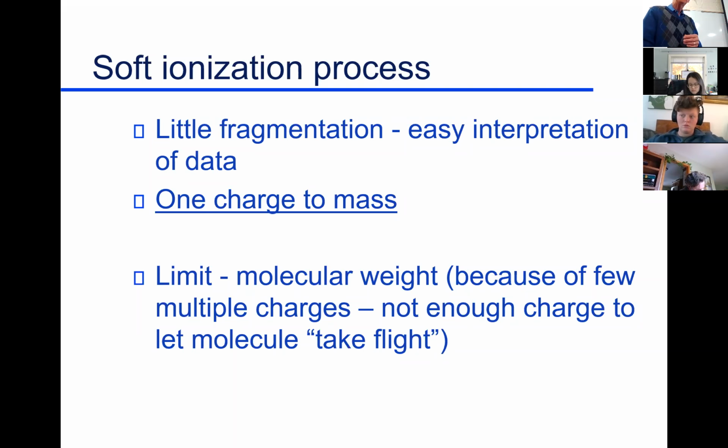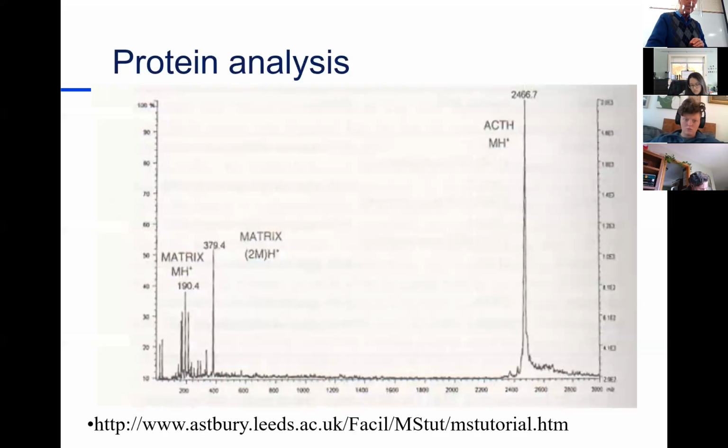The only problem that we have is it is limited in molecular weight. To measure any of these molecules and fragments, I've got to get them into a stream. It's a vacuum, but I need to have them moving. And a protein's a big molecule. I have trouble getting it moving if I've only got one electrical charge on it, and so I'm limited in mass. I can't do very, very large proteins. So I have to use, again, a different technique that puts multiple charges on. But it's a beautiful, simple technique. You get nice data from it if you're not getting too big or too small, kind of mid-range.